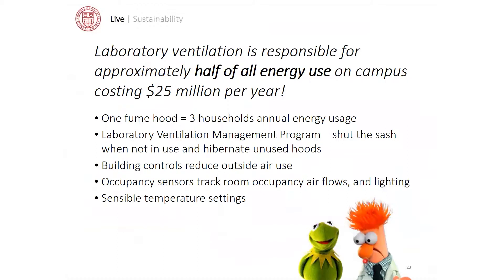Lab ventilation is responsible for about half of all campus energy use. One fume hood is about three households worth of energy use. We have great programs to help folks better manage their fume hoods — we have a full-time staff person whose sole responsibility is this. We also look carefully at how building controls are set up — whether air changes are really tailored to what's happening in the fume hood, sensible temperature settings, and occupancy sensors. These have made a big difference in controlling lab energy use, and they can have a potentially very large impact on our climate goals.